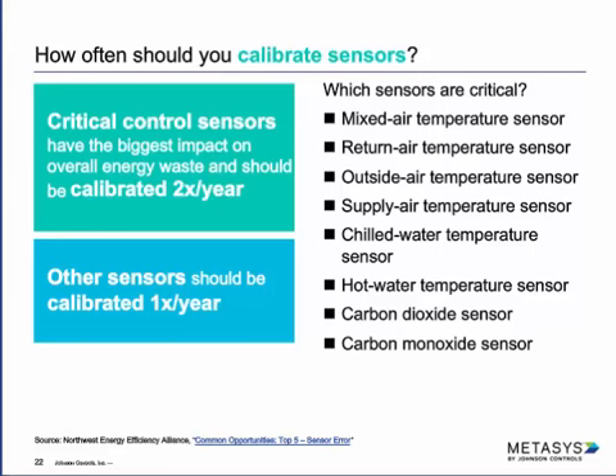Critical control sensors, sensors that are actually involved in the sequence of operations for the equipment—you've got a list here on this slide—really need to be calibrated twice a year. Now, as new sensor technology evolves, we're seeing more self-calibrating sensors.